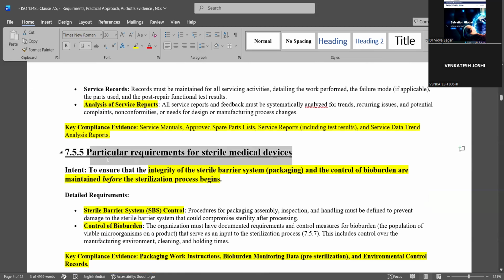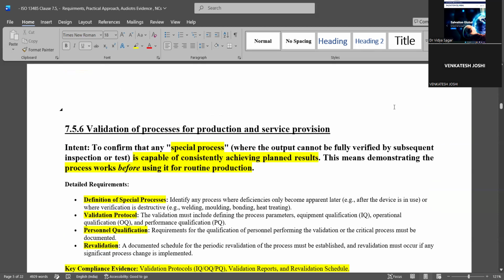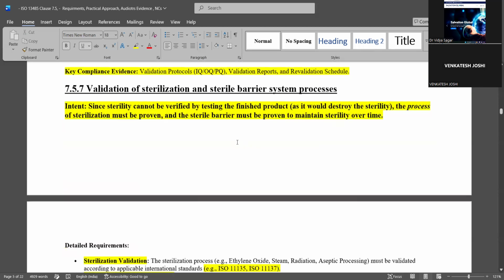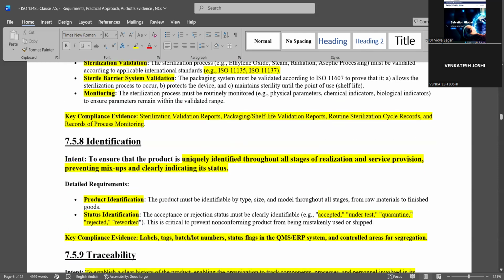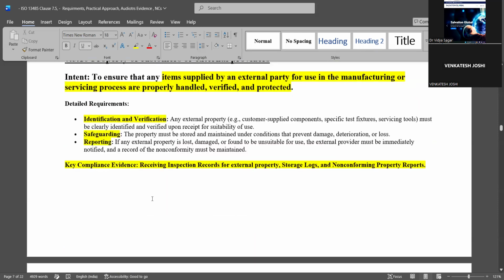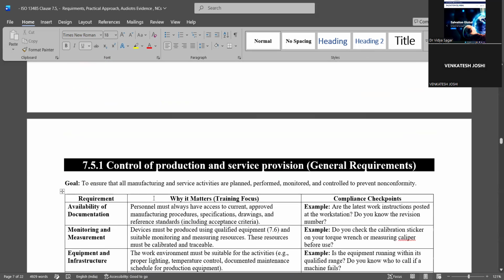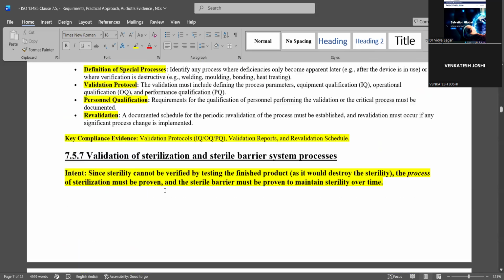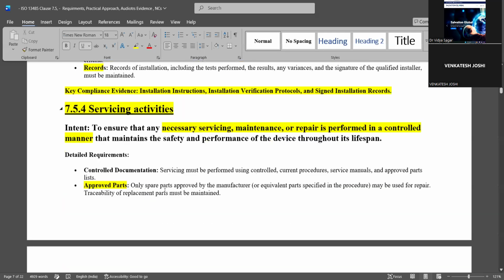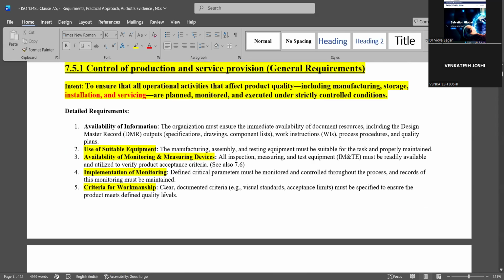This is regarding sterile medical devices. What are the requirements for sterile medical devices? Then comes the important one, validation process, validation of sterilization, identification, traceability, property of customers, preservation of product. So you have a lot of subclauses in 7.5. See, clause 7 is a big one. You have 7.1, which talks about planning, and 7.2 talks about customer communication. 7.3 talks about design and development. 7.4 talks about purchasing.